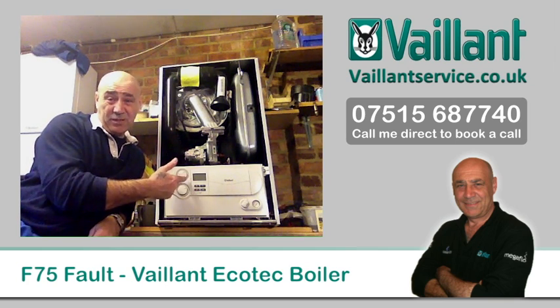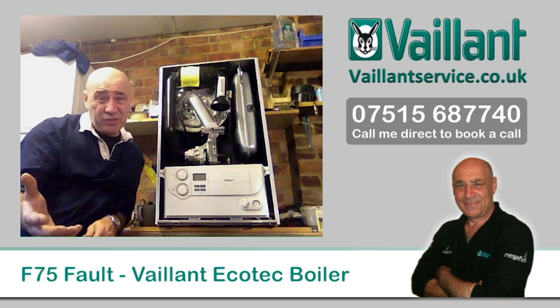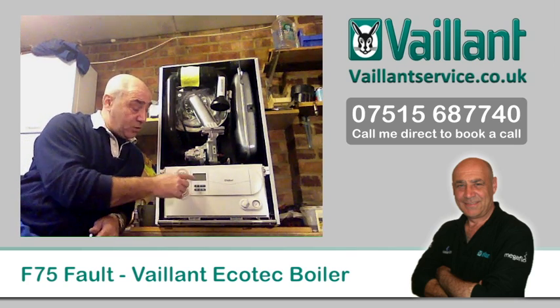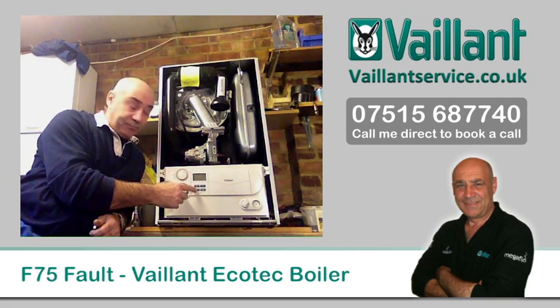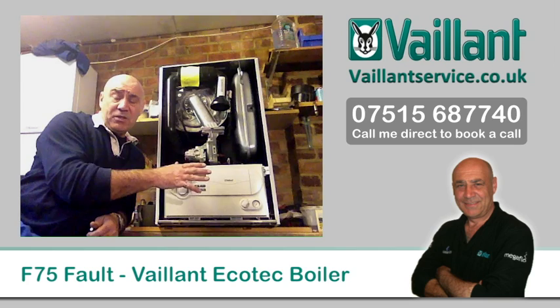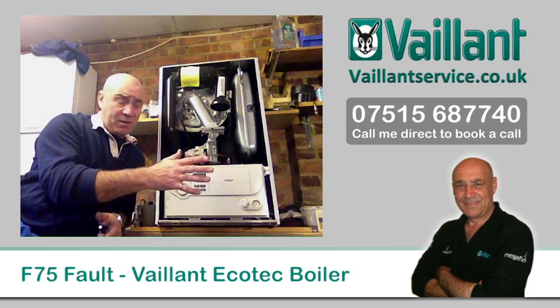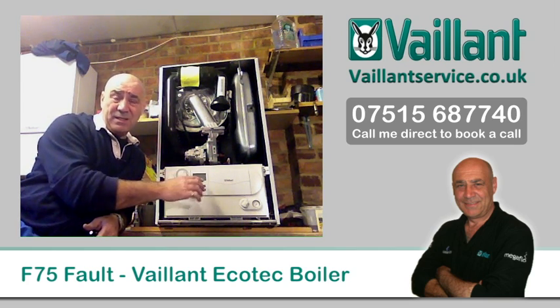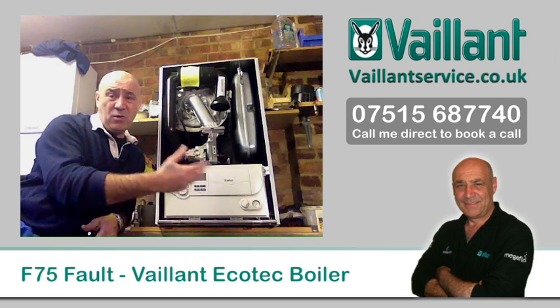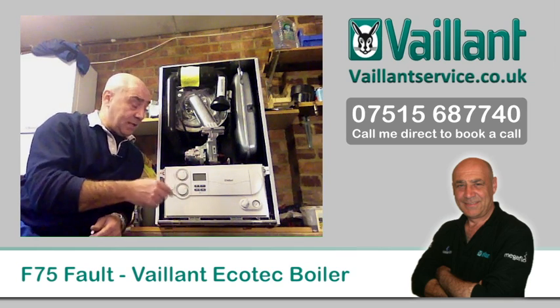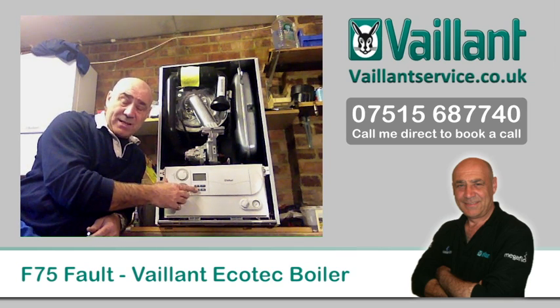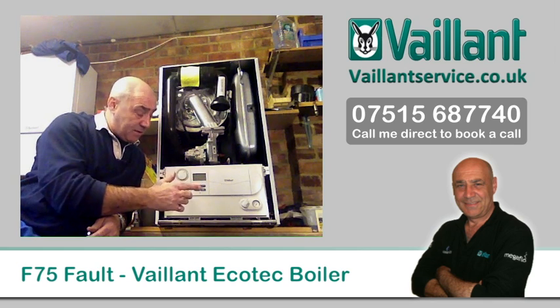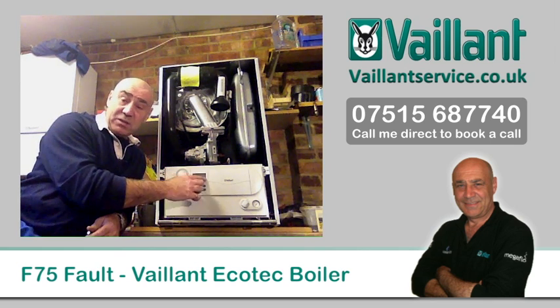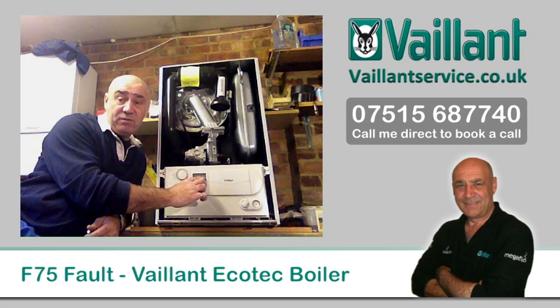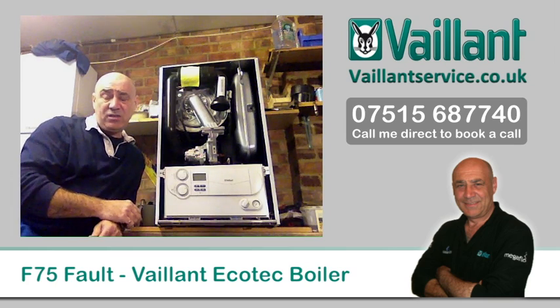I can't use it on this one because the boiler's not powered up, so I can't show you, unfortunately. But normally in the display you will just have the temperature of what the boiler's doing at that time, plus a couple of indicators under there showing whether you've got the warm start on, the heating on, the hot water tap, and the temperature. If I push the minus button in until it clicks, hold it in and release it, after 3 seconds the display will change and give you the pressure reading from the electronic sensor inside.